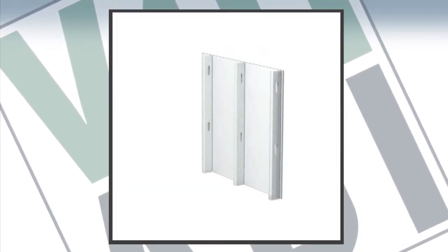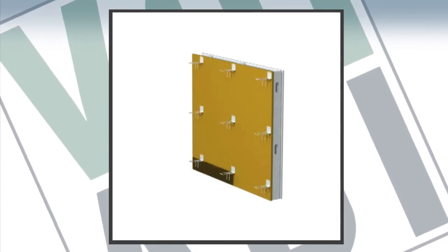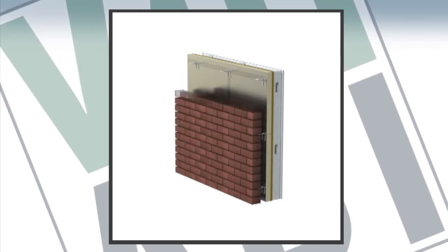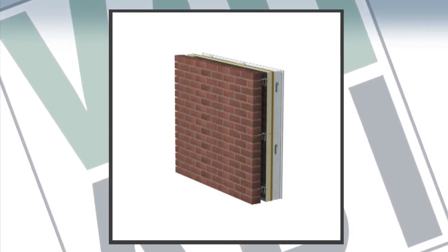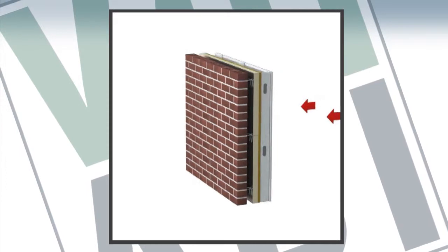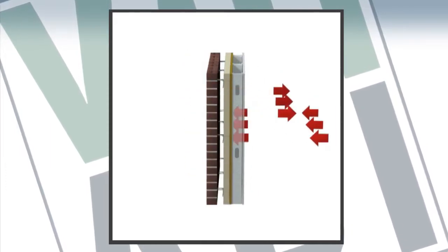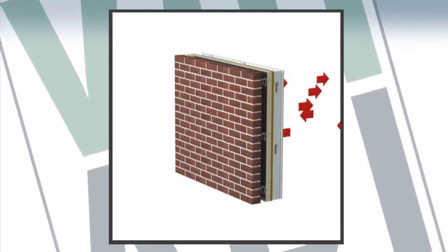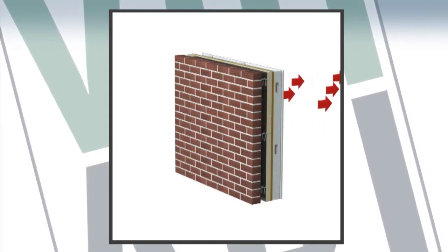Continuous insulation is defined by ASHRAE as insulation that is continuous across all framing members, eliminating any thermal bridging in the structure. And there would not be any penetrations in the insulation with the exception of fasteners or service openings. Continuous insulation can be installed on the interior side of the wall, the exterior side of the wall, or integral to any opaque surface on the exterior of the wall.